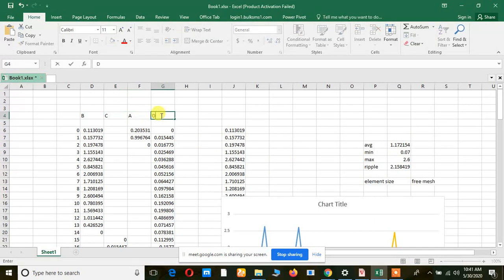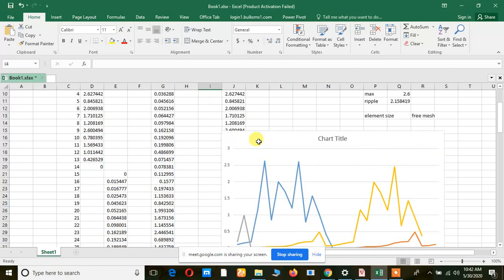So now we have obtained the sequence order. And this is coil 1. So coil 1 is phase B, coil 2 is phase C, coil 3 is phase A, and coil 4 is phase B. So this is how we have to identify the phase, which is phase A, which is phase B, and which is phase C, right?